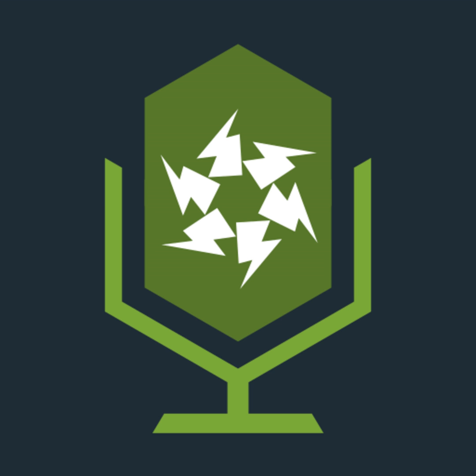So we'll see supplies in there. What is their earthing arrangement? What is their supply protective device? Their number and type of live conductors. And then we also consider what they want of the electrical system. What is their maximum demand once we've applied diversity? How will we achieve compatibility with the existing systems? How will we achieve maintainability? All of those questions we have to ask ourselves at the initial point are in assessment of general characteristics.